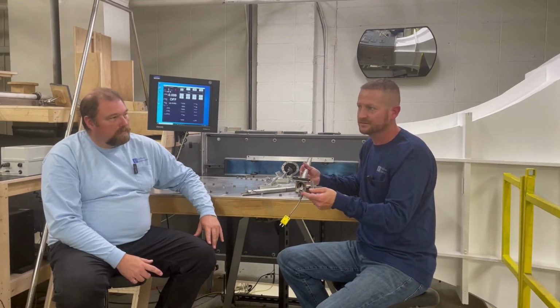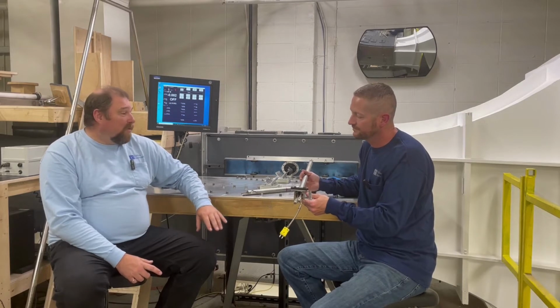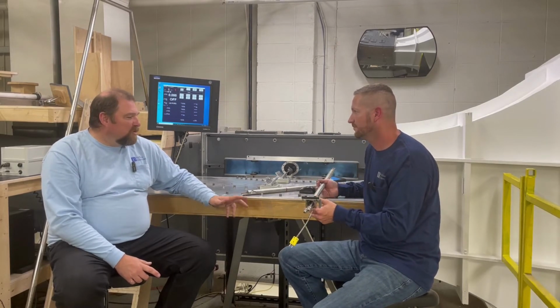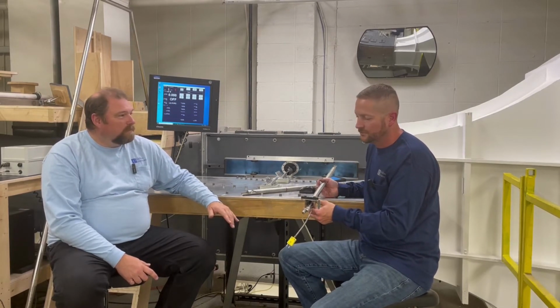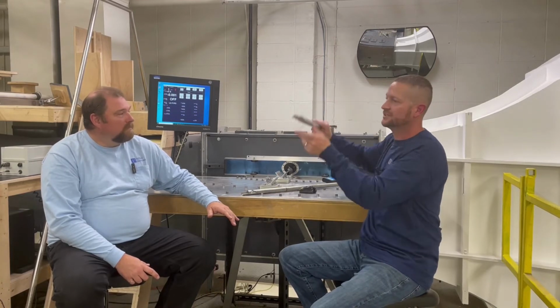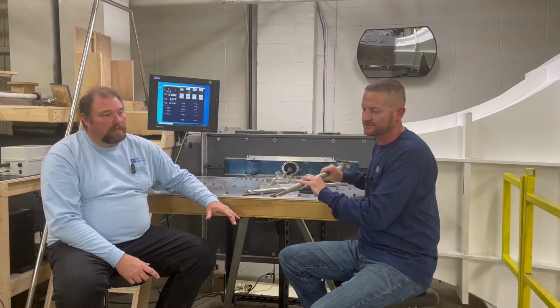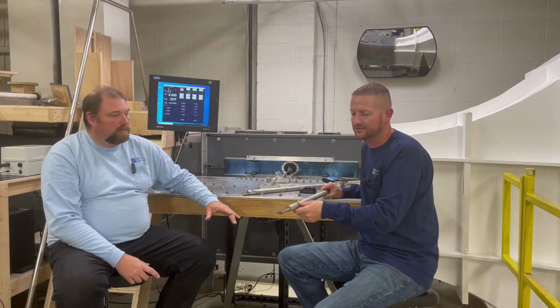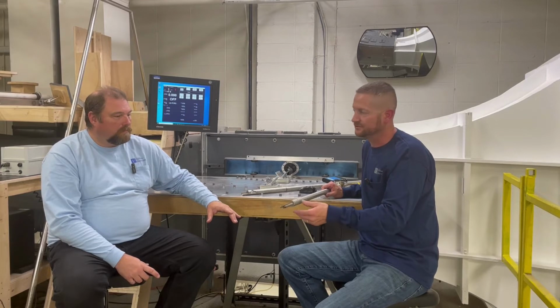Before you actually do a calibration, is there a procedure that's done here? Before we'd calibrate this probe, we would want a leak check across the pressure lines to make sure there's no leaks, and then do an inspection of the probe head based off of EPA procedures.